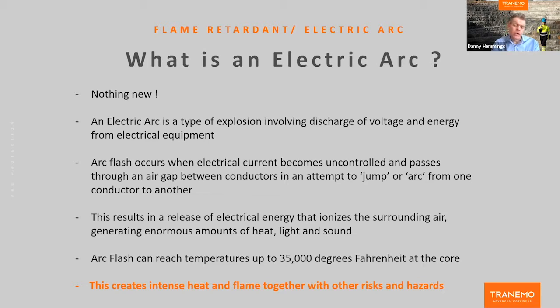And they've really, the wherewithal has grown in an exponential way, particularly, I say, over the last 5 years. But if we look at the principles of an arc, in its simplest form, it's an explosion where there's a discharge of voltage and energy from electrical equipment.